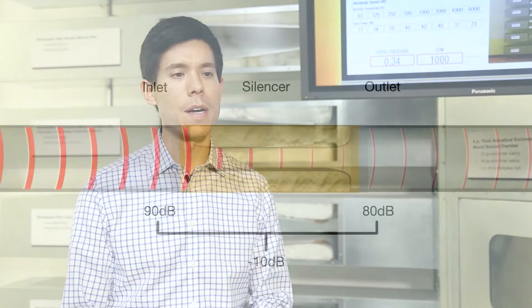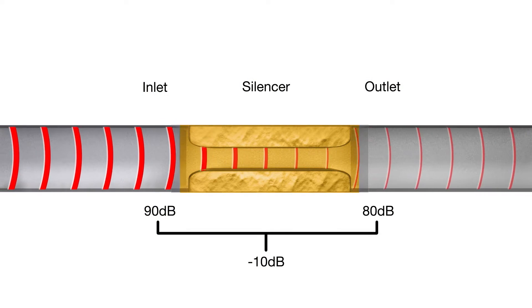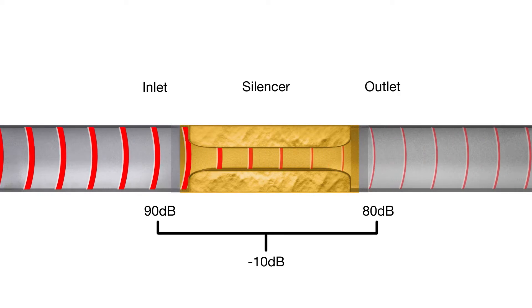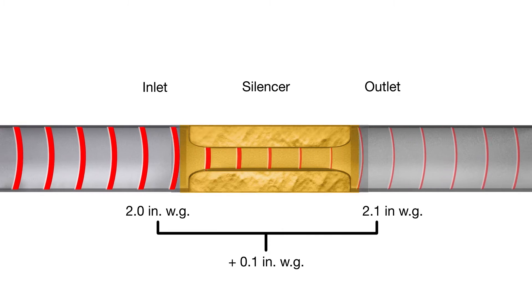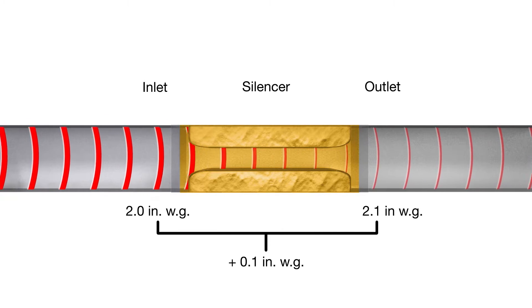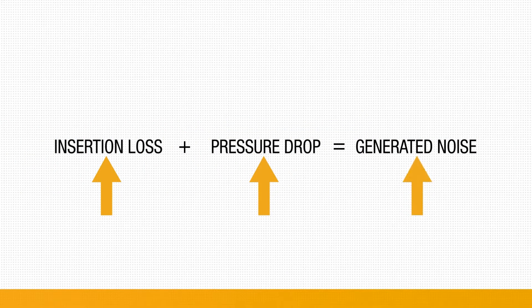Silencer performance is typically described using insertion loss and pressure drop. Insertion loss is the decibel reduction in noise across the silencer and can be thought of as a negative value. The pressure drop is the silencer's differential static pressure and is measured a minimum 5 equivalent diameters upstream and 10 diameters downstream of the silencer. Typically, as the silencer's insertion loss increases, so too does the pressure drop and generated noise.